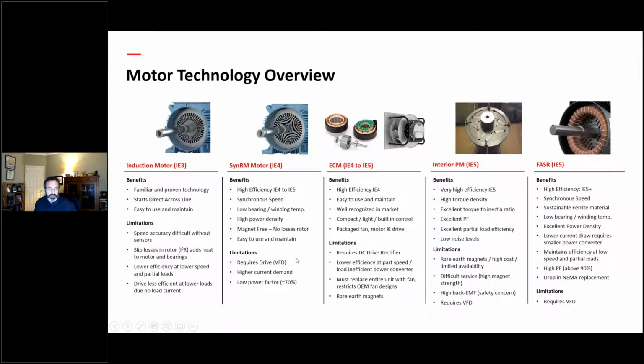So here are the motor technologies that have been applied into industry today to address the higher efficiency. I've already talked about standard induction motors and premium energy efficient motors. It's a familiar and proven technology. It starts across the line. So that's a really big advantage, because you don't need to have a variable speed drive on that. Although as you know, if instead of doing mechanical dampers or valves or throttling control, when you put a variable speed drive on it, you can save a considerable amount of energy. So it's debatable whether running across the line is a big advantage when you're talking about trying to save energy. It's probably better to put it on a drive.